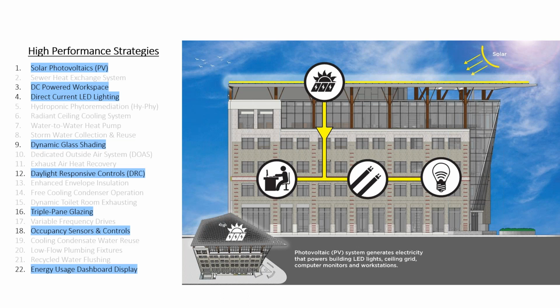The photovoltaic system is installed on the roof horizontally, but it's also installed vertically on the south side of the roof because the design team needed to increase the amount of surface to meet a certain power requirement, to make sure that the net zero energy requirement is met. So implementing the 22 high-performance strategies will provide the AGU with an annual building energy consumption of not more than 300 megawatt hours annually. The PV system itself will be able to provide almost 346 megawatt hours of energy. Next, please.